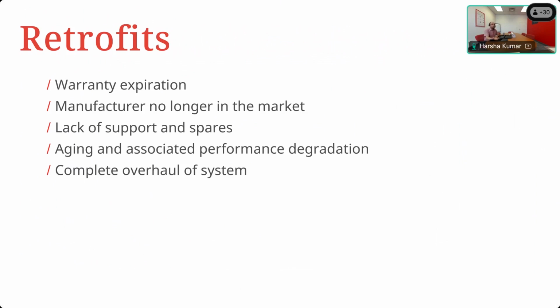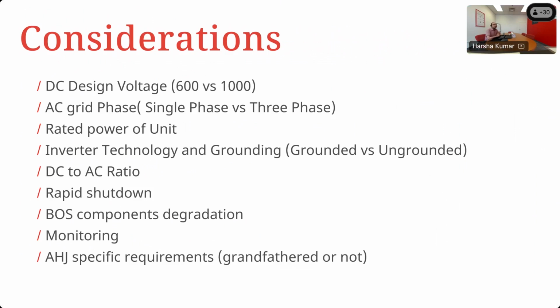So now, if I'm going to pull out a transformer-based inverter and stick a transformer-less inverter in there, there are certain checks and balances you have to do if you don't want to lose an inverter. Those are what we call considerations. In addition to that, there are a few other considerations as well. You have to remember that back in the day, hydro would not let you go beyond 600 DC, or ESA would not let you go beyond 600 volts on the DC side. That isn't the case anymore.